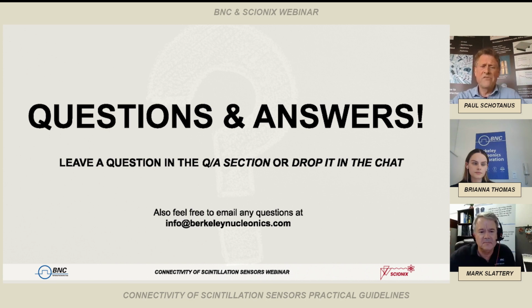If you're looking at events that generate very small amounts of light, for example, if you have a classic sodium iodide scintillator, you're looking at iodine-129 at 30 keV, and you have a sizable scintillator, let's say 100 cc, then at elevated temperatures you really have a problem with noise and you cannot see 30 keV anymore. But for other applications, it will be perfect.